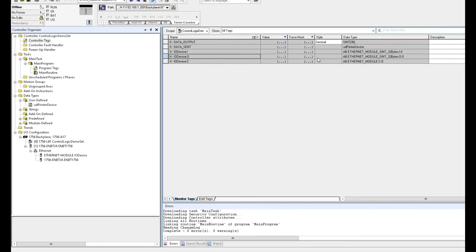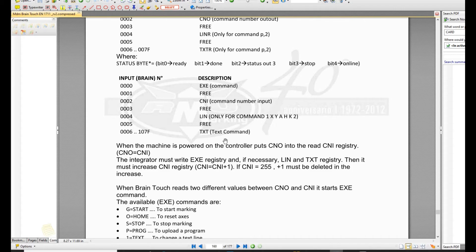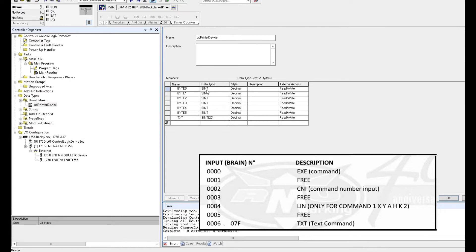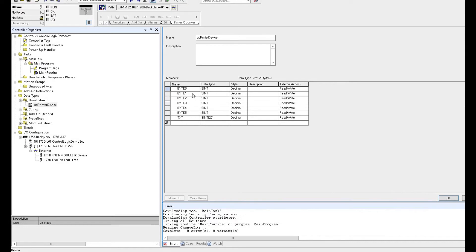The unit is bytes. Based on this device manual, to control this device, the top six bytes are a command, and the following bytes are text. Following that manual, we create one UDT. From index zero to six, that is a byte. And the following structure is text — I leave a 20-byte buffer to send the text tags to this device. That is the UDT structure.